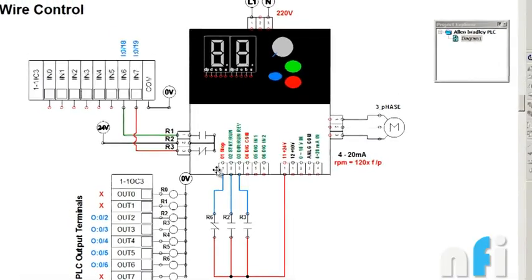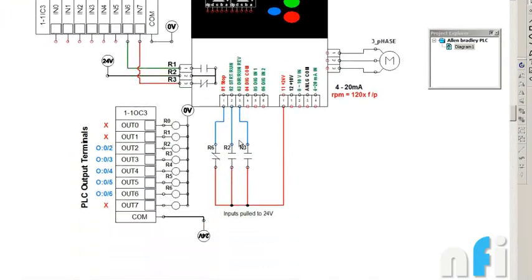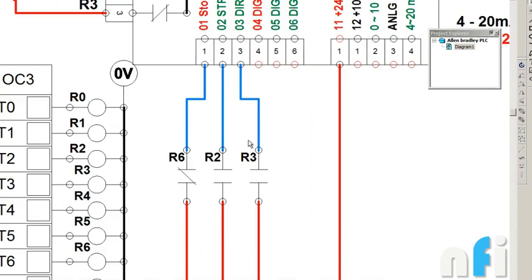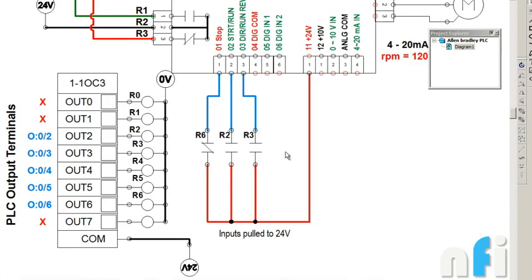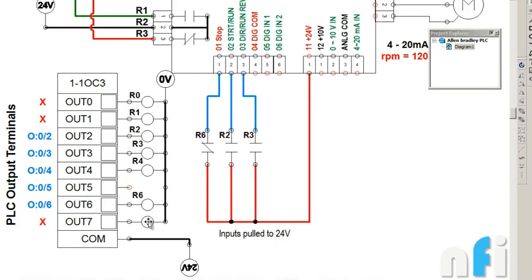This is the wiring diagram for three-wire control. In three-wire control we are using terminal 11, which is 24V source input, connected to relay contacts R2, R3, and R6. We are using three relays: R2, R3, and R6. Let's remove the other one to avoid any confusion.